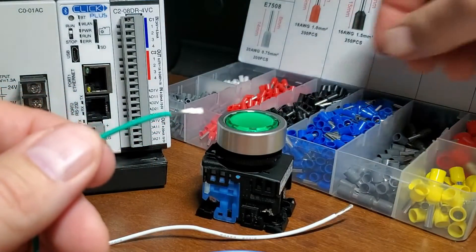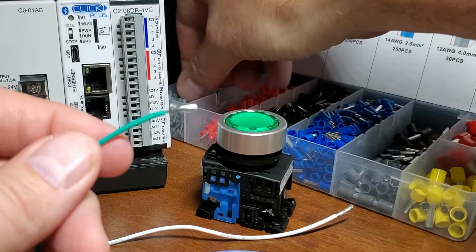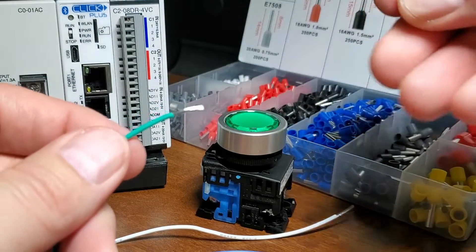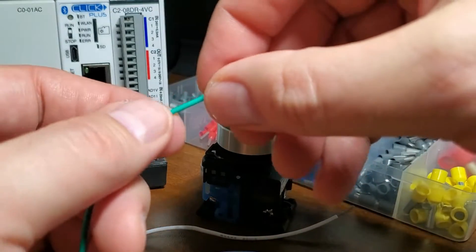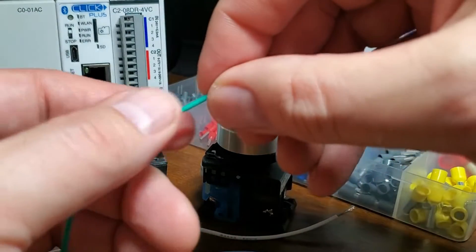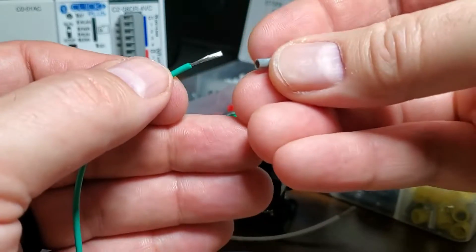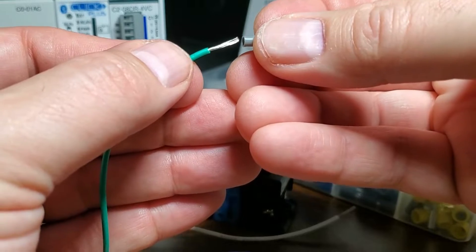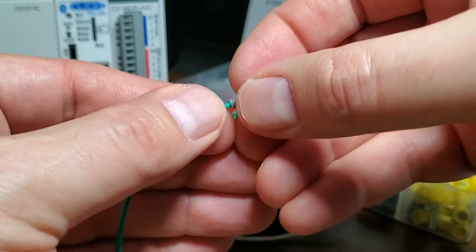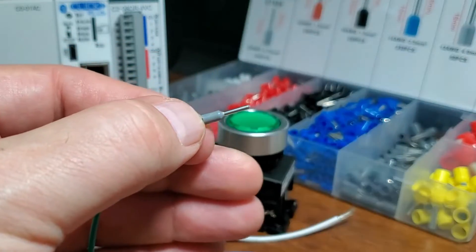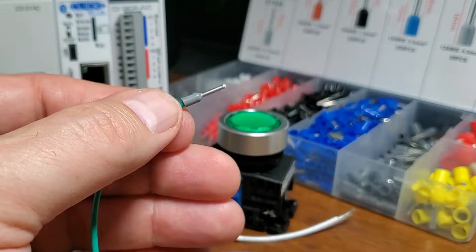A ferrule is a thin tin-coated copper cylinder placed over a wire-stripped end. The ferrule crimper will compress the tube into a square or hex shape, depending on how the wire connection is used.